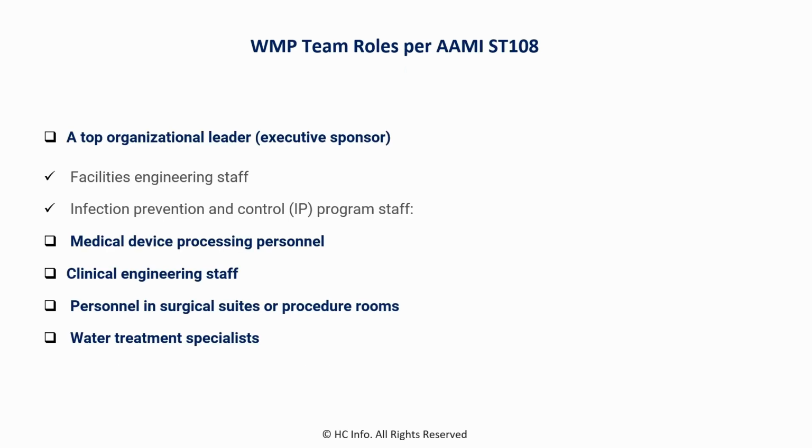A little discussion on the water management team roles that AAMI requires. I thought this would be helpful. I used a check mark for ones that typically people already have in labs, and boxes as a checklist for the ones that are going to be needed to add if you don't already have them. They do call out a top organizational leader. This would be an executive sponsor, typically someone in the C-suite. They have the authority to make critical decisions regarding water restrictions or other emergency response measures. They also are able to allocate necessary resources, whether that be financial or personnel.